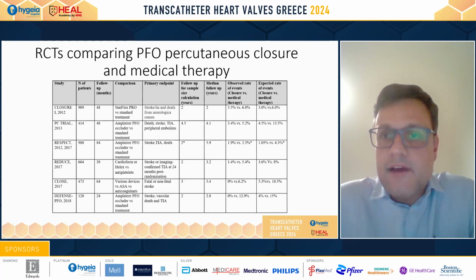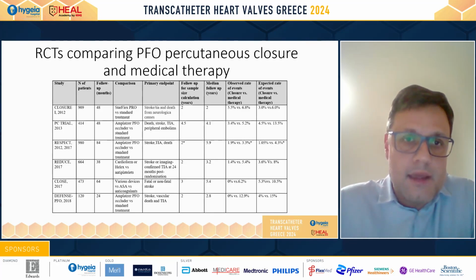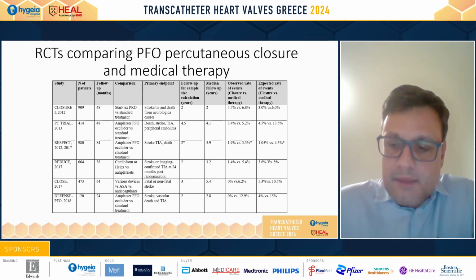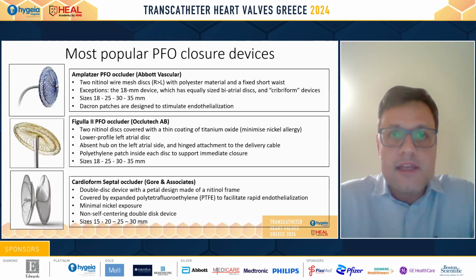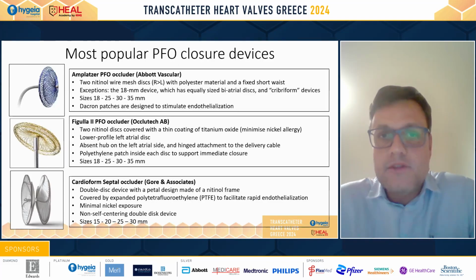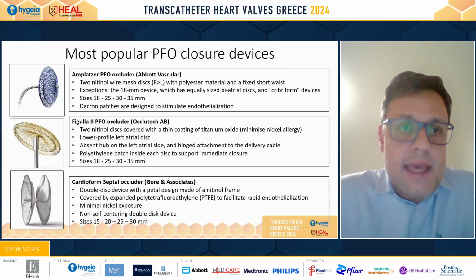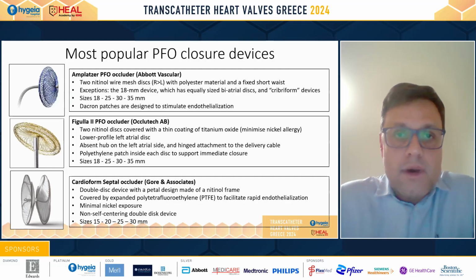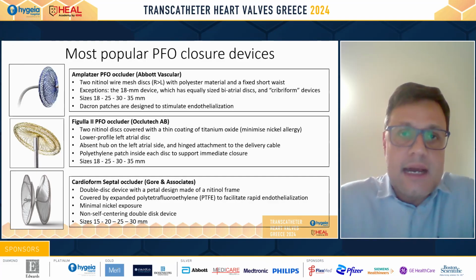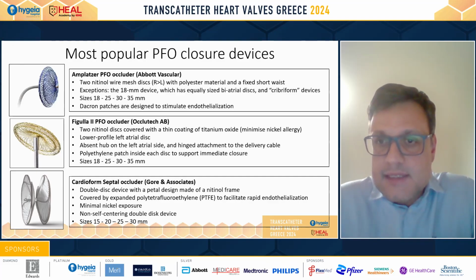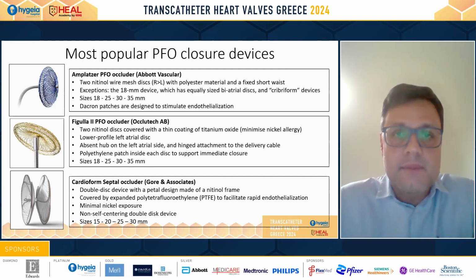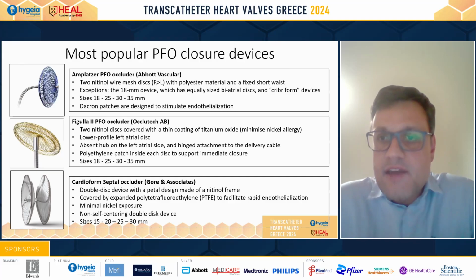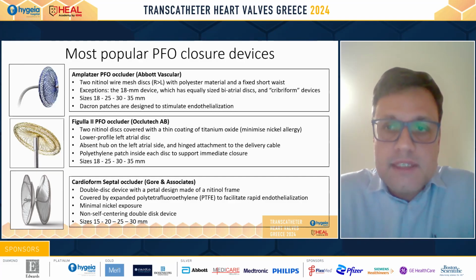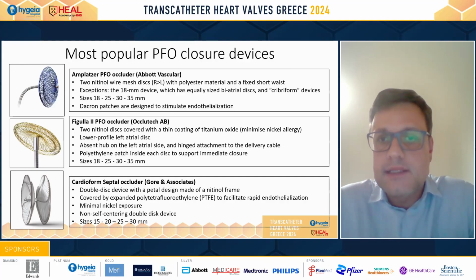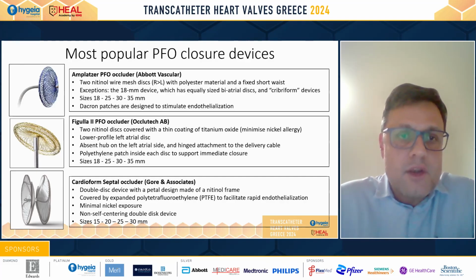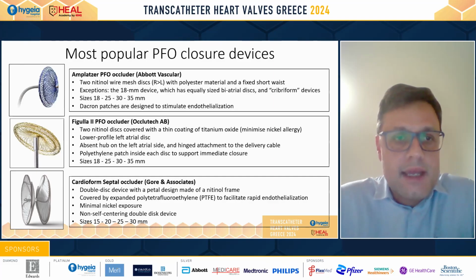These RCTs have used different devices, and let's have a deep view of the most common of them. Starting with the Amplatzer PFO occluder from Abbott. It consists of 2 nitinol wire mesh discs. The right disc is larger than the left disc, apart from the small device, the 18mm device. There are 5 devices that can cover all the anatomies, and of course the device is covered with Dacron that stimulates endothelization.